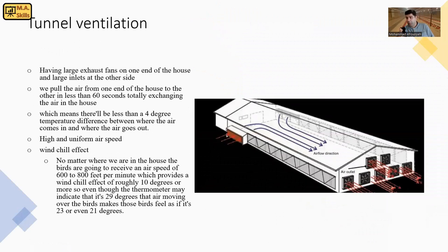To explain more about tunnel ventilation - tunnel ventilation is simply having large exhaust fans on one end of the house and large inlets at the other side. We need to pull the air from one end to the other in less than one minute, exchanging the total air in the house, which means there should be less than 4 degree temperature difference between where the air comes in and where it goes out. This is really important. By tunnel ventilation, we create a uniform environment in terms of air temperature, especially during warm weather.